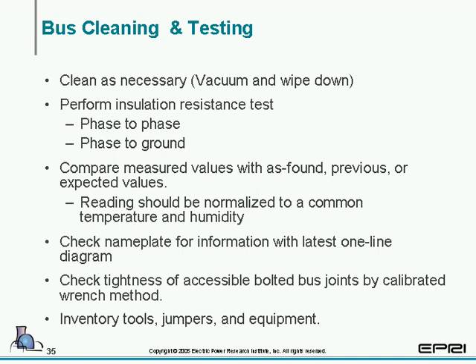We take a look at cleaning. Basically, we spoke about it in session 2. For cleaning, you want to use the least aggressive method possible. You either want to use a dry rag to remove dust or whatever is on the insulation or the bus. If that can't be done, then you're going to use denatured alcohol. If you use anything stronger than denatured alcohol, you're going to want to go back over it with denatured alcohol and a dry rag to remove any type of residual.